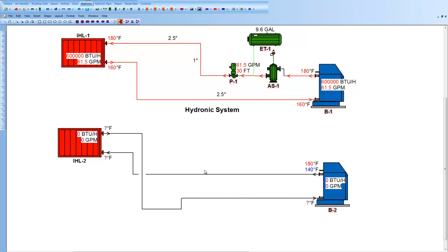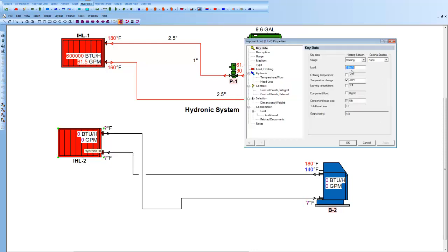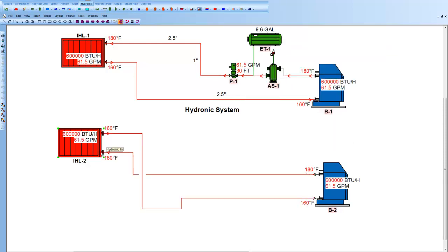Now, the pipes are black. That tells me no information is being transferred. Every component is intelligent and smart. So I can double-left-click on the component, and come in here, and type in the load, 600,000 BTUs, and hit OK. And you'll see that that load information has been transferred down.